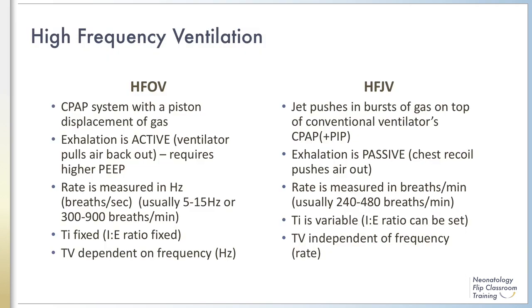While the physics behind high-frequency ventilation are the same for both the oscillator and jet ventilators, their systems and settings differ. The oscillator is a single ventilator system that uses a continuous pressure and a piston to create the displacement wave of gas. Because of the piston, exhalation is active — when the piston oscillates away from the patient, it pulls the air back out for exhalation. The active exhalation requires a higher PEEP to maintain it. The range of breath rates is larger for the high-frequency oscillating ventilator, often expressed in hertz — breaths per second — rather than breaths per minute.